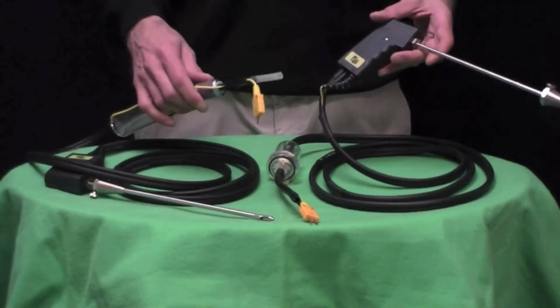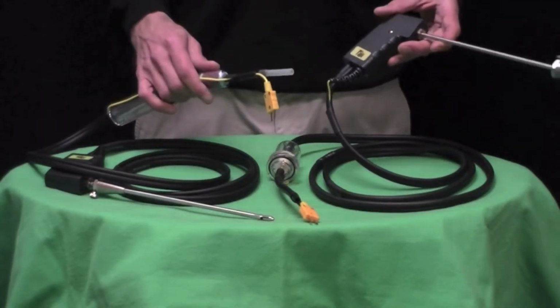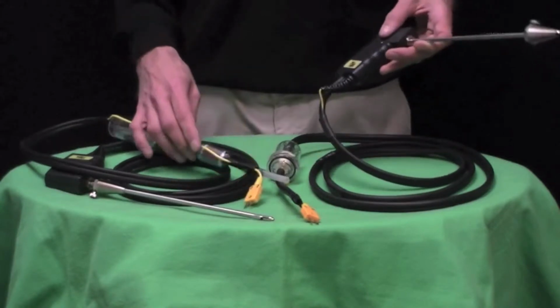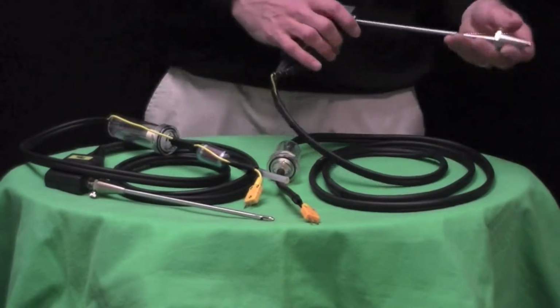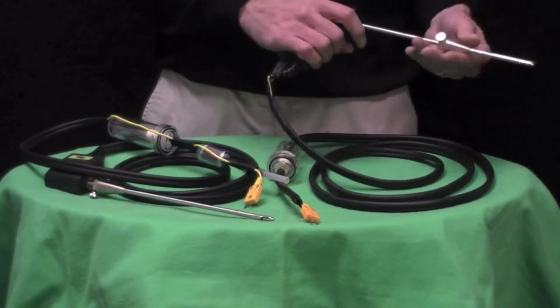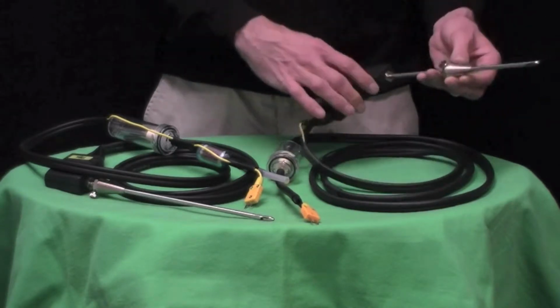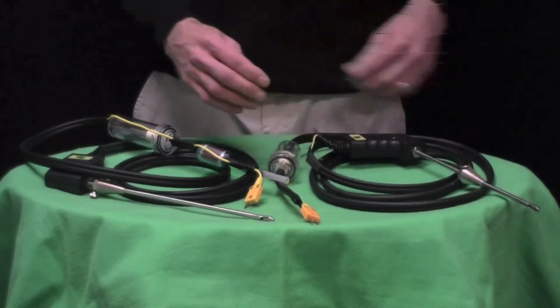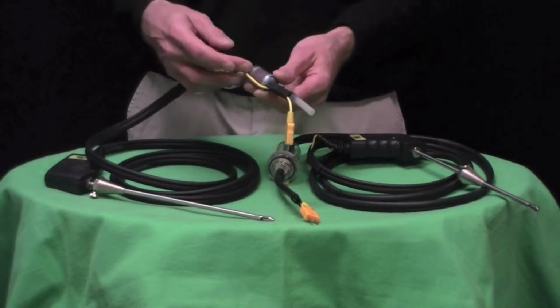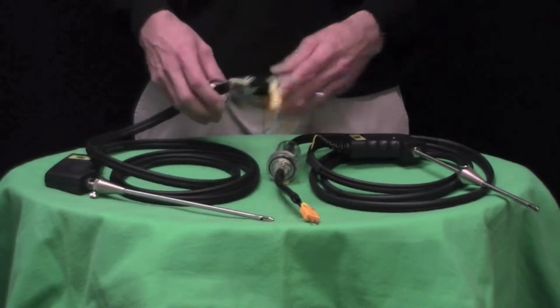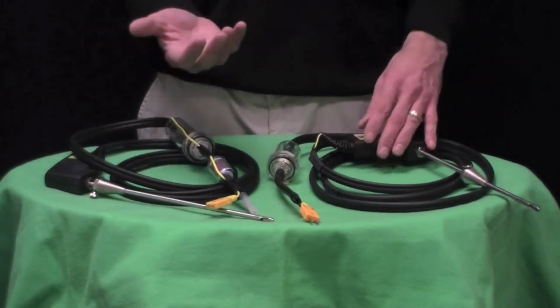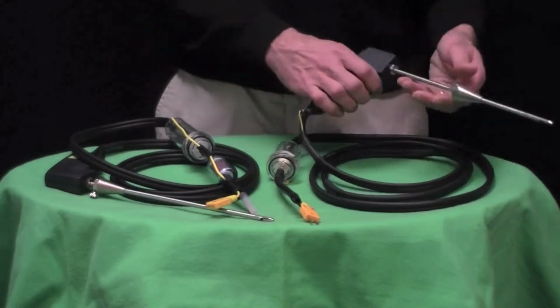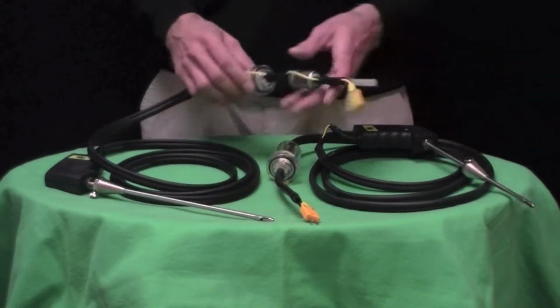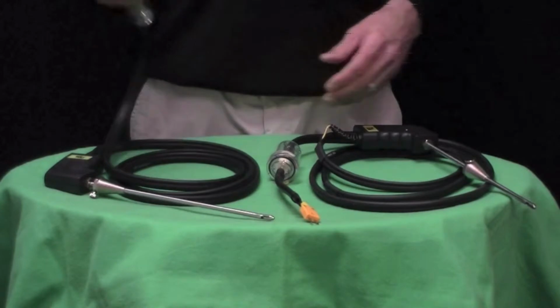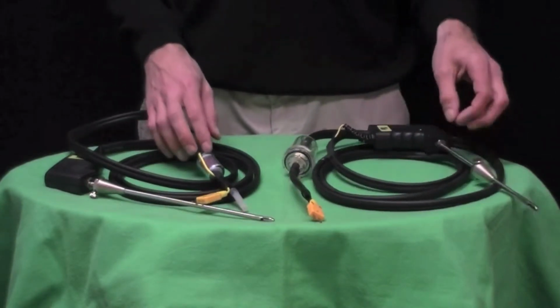The proper orientation for the A773 Sulfur filter. The A773 Sulfur filter is needed when you're using a 700 series combustion analyzer for work with oil-fired equipment. It takes all the nasty stuff out and enables clean flue gas to go into the analyzer without causing any problems. So an A773 is required when working with oil-fired equipment.